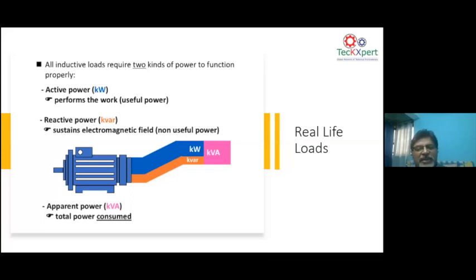The reactive power is where it has gone. It has gone into the motor's magnetic field, because unless you create a magnetic field, you will not get a rotary force. The power which is stored in the magnetic field becomes your reactive power. So the total power consumed by a motor is a sum of active power and reactive power. If you have a motor with a good power factor or an energy efficient motor, it will draw less reactive power. That means your transformer or generator is less loaded by the motor load.